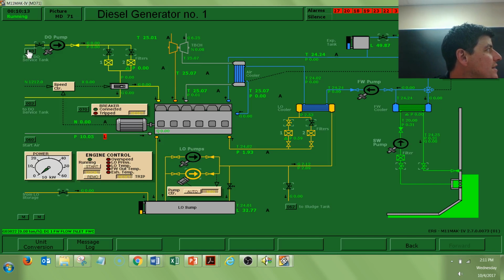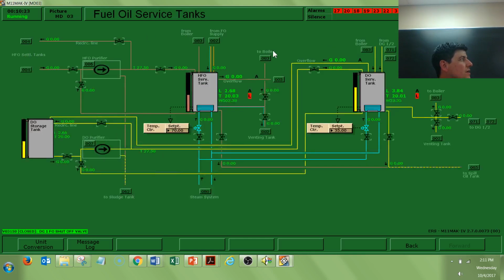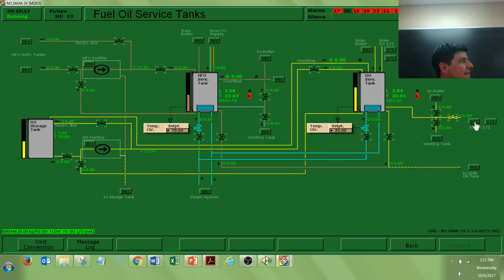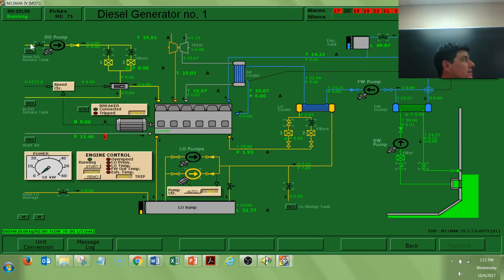On my fuel side, I've got a pathway for fuel. It doesn't start here. We always have to backtrack to the very starting point. So I start from the diesel oil service tank and make its way to the diesel generator. All the way through. So when I get to the point of having 15 bar, I believe I should be able to get this started. If I wanted to, I could repeat the process with my other diesel generator, but I'll just concentrate on the first one right now.